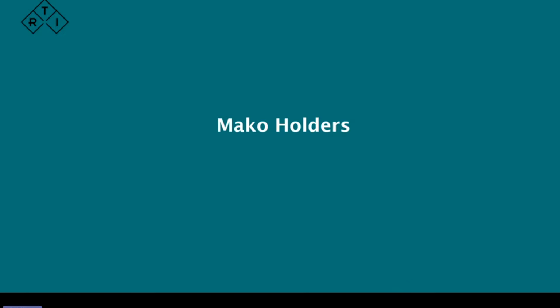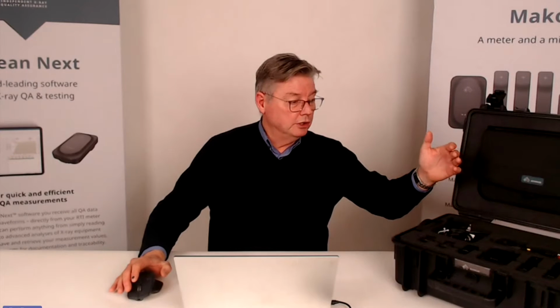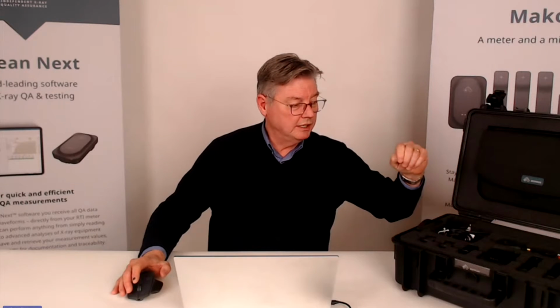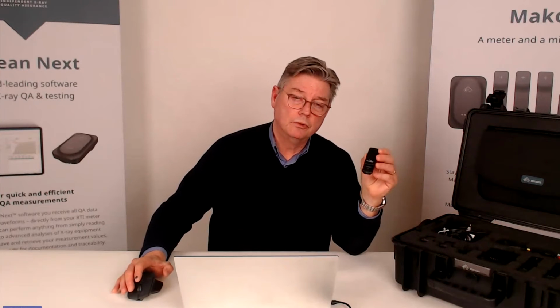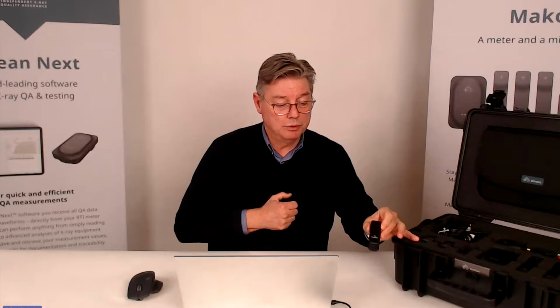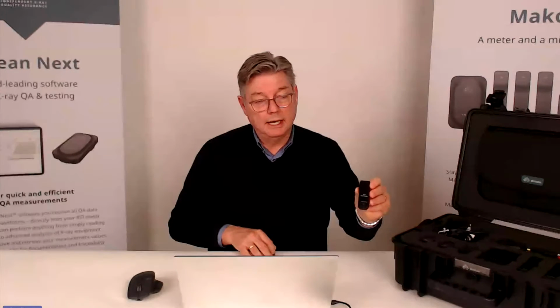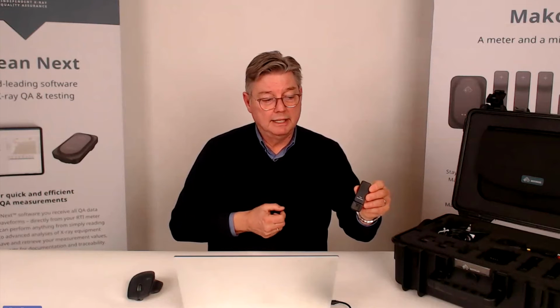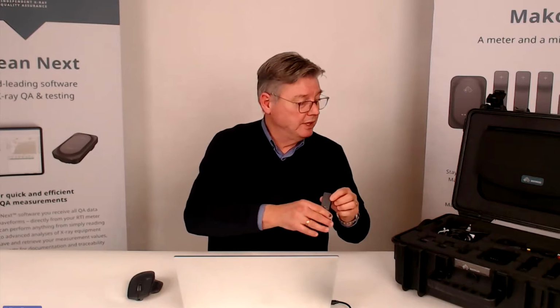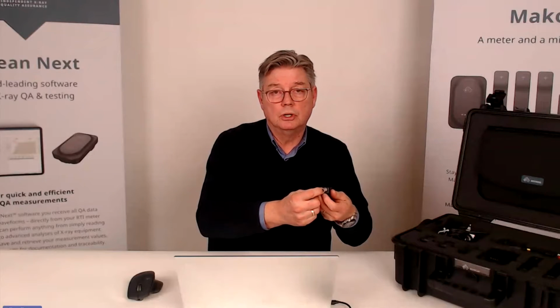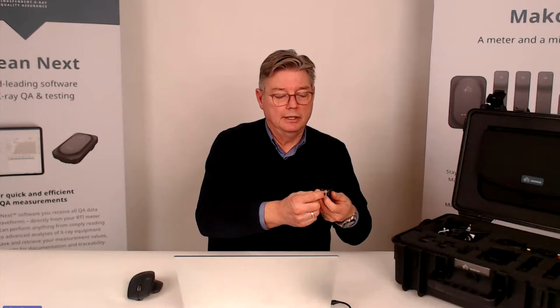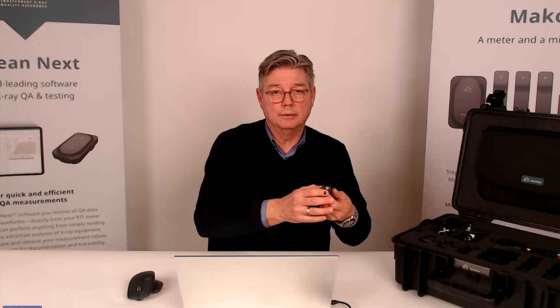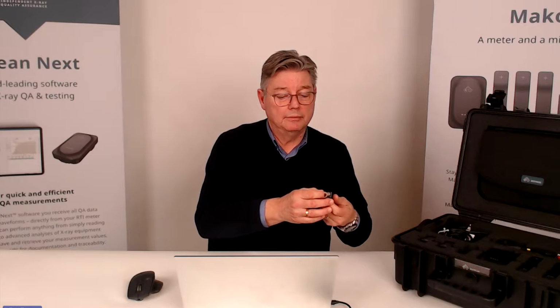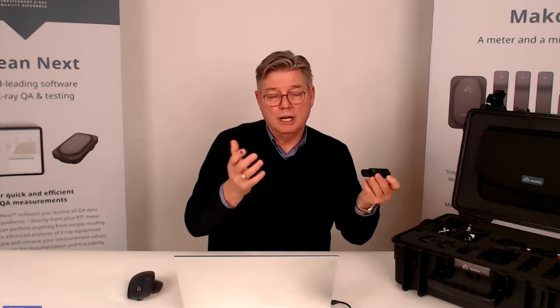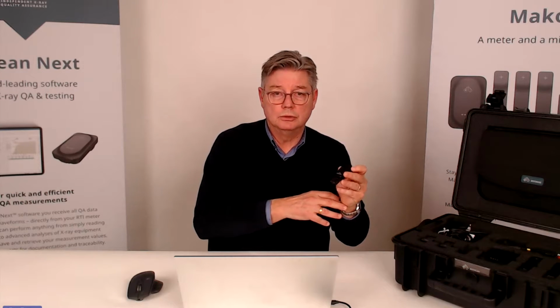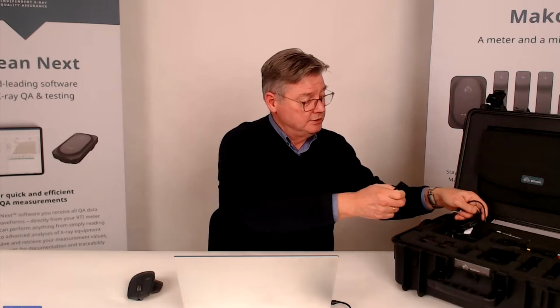All right, before we move into the holders, I'd like to talk a little bit about, we talked about the base unit, we talked about the probes we have, then we also got some modules to make up that wide application range we were talking about. The first one is the ion chamber module, and as the name indicates, it's meant for ion chambers. The connector is LEMO, so the standard RTI CT ion chamber, for instance. The DAP chambers that we provide will be managed here, as will the mammo chamber that you can buy from RTI. But also other manufacturers, if they have a LEMO connector, will be able to function with the ion chamber module.